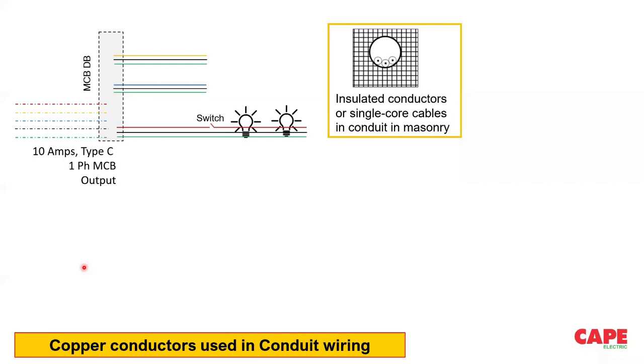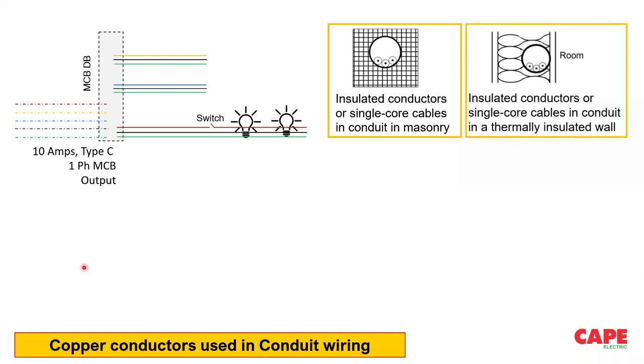Of course, for industrial, it's a little bit different. But whatever type of MCB you use, you have to size the conductor accordingly, and you have to have the impedance accordingly. Number two, copper conductors used in conduit wiring. You know very well conduit wiring. I have spoken about this subject on several occasions, not now for the first time. Copper in the wire generates heat. Once we pull the copper wire through an enclosed space, such as a conduit or a trunking, the amount of heat which can be generated inside this confined space must be limited, say, for example, not more than 70 degrees. If the temperature goes more than 70 degrees, you end up with trouble.